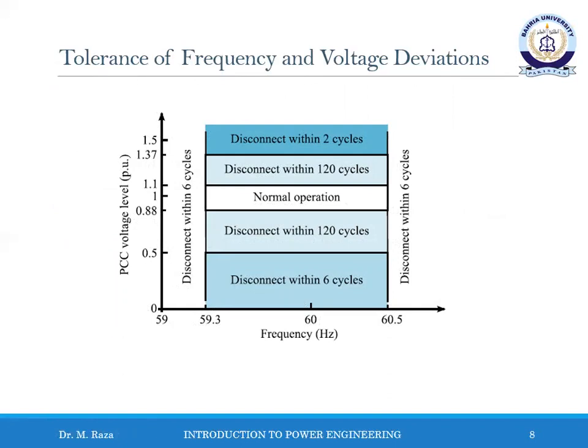The operational characteristics of PV distribution power generation system with respect to frequency and voltage deviation is illustrated in this diagram. This example is for 60 Hz system in which PV generation system should continue working as normal operation within the frequency range between 59.3 to 60.5 Hz, and the PCC bus voltage should be between 0.88 to 1.1 per unit. The PV system should disconnect within the 6th cycle if network frequency drops below 59.3 Hz or rise above 60.5 Hz, such as shown over here.